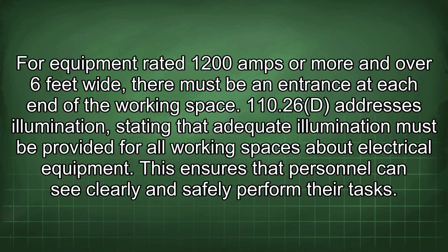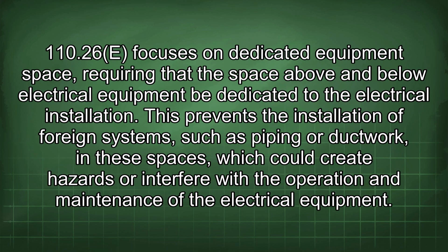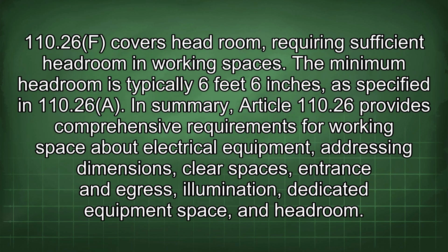110.26d addresses illumination, stating that adequate illumination must be provided for all working spaces about electrical equipment. This ensures that personnel can see clearly and safely perform their tasks. 110.26e focuses on dedicated equipment space, requiring that the space above and below electrical equipment be dedicated to the electrical installation. This prevents the installation of foreign systems, such as piping or ductwork, in these spaces, which could create hazards or interfere with the operation and maintenance of the electrical equipment. 110.26f covers headroom, requiring sufficient headroom in working spaces.